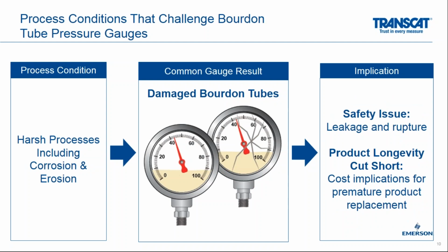And then the final thing that's very common is harsh pressures, or harsh processes, I should say. And this is different from just really high pressures that can, you know, explode, essentially. With harsh processes, we're talking about corrosion and erosion. And you need to make sure that the gauge, the actual Bourdon tube that the fluid or gas is going in, can meet any sort of those harsh processes or chemicals, acids, whatever they are. And if you do get a damaged tube, just like an overpressure, it's a safety issue because that same content is leaking out of your process and you need to replace the gauge. What makes this one even more unique is unlike a high pressure piece where the safety issue might be more immediate, if it's something that's very corrosive or it's possible that it's actually a bad chemical, there could be some long-term effects if this leaks out.